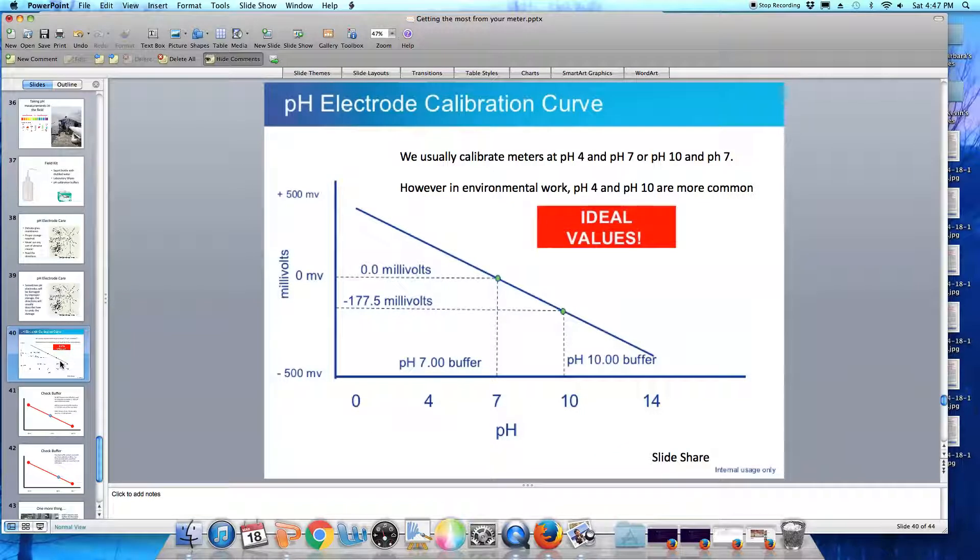Let's talk about the pH electrode calibration curve. Most of the time, when you're working in a laboratory, you're going to know whether your pH readings are going to be alkaline or acidic. So the first buffer we put our probe into for calibration will be neutral pH 7. And in this example, the pH 7 buffer will generate an electrical signal of 0.0 millivolts.